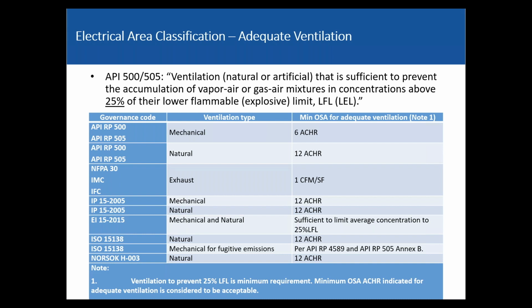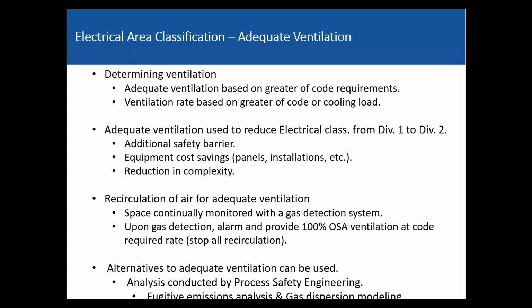So anyway, next slide. All right, how do we determine ventilation? Just normal HVAC stuff. We look at our prescribed adequate ventilation, which we calculate. And then we look at cooling loads. We may have adequate ventilation at 6 air changes an hour, but the cooling load of the module requires 12. Covered.